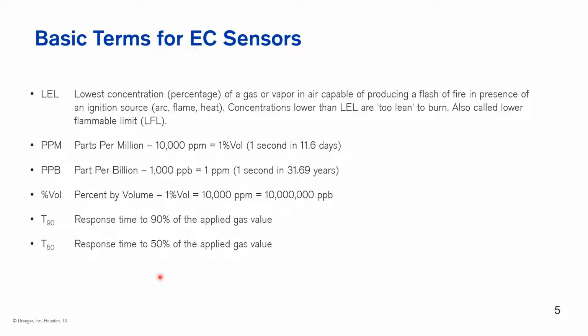And this is important. Just recently, I was working with a customer on some SO2 detection, and the instrument that he was trying from another manufacturer had a response time that he was telling me was in the 90-second range to get to 90% of his reading. And our sensor, the specification is less than 15 seconds to get to 90% of the response.